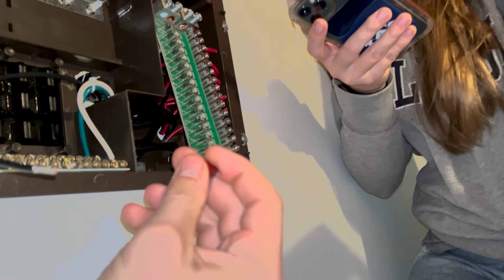Take us to your meter. Here you see us putting the wires into the AC output side of the inverter. Neutral is white, green is ground, black is live. We used a screwdriver to tighten all of these connections.